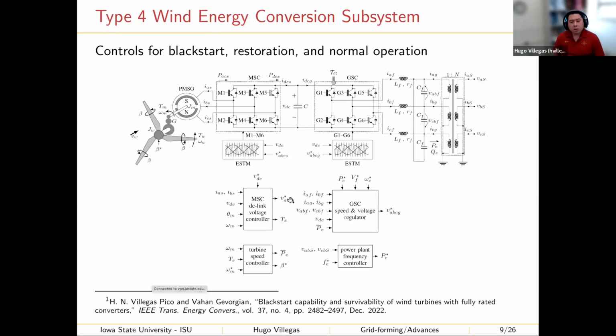Okay, so what we have done here at Iowa State is that we have designed four control blocks to steer, for example, the Type 4 wind turbine that we are showing here in this picture. This wind turbine has the grid side converter and the machine side converter. It has a step-up transformer that interconnects to the distribution system, and it also has a pitch angle control of the wind turbine. And of course, here it has a permanent magnet synchronous generator.